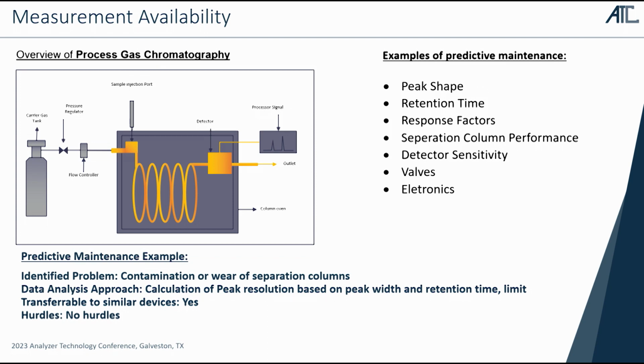Gas chromatography, especially, is already providing far more data than you can actually process. Some of the devices are capable of providing 20, 30, 40 diagnostic parameters to a software to analyze. And in the field of gas chromatographs, you can also cover all the physical components. Of course, all the peak characteristics we have, retention time, response factor, but also how well the separation column is performing, the detector sensitivity, the valves, the electronics, and so on.